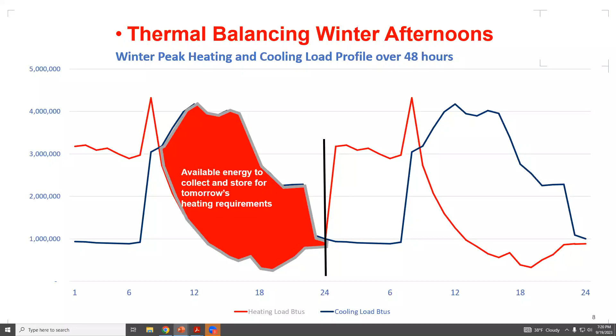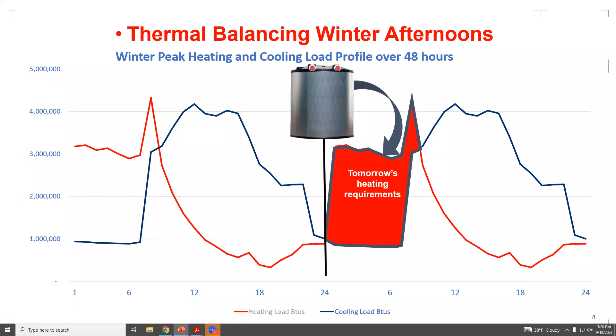Just to clarify, you're modeling a typical office building with an interior zone and an external zone. Yeah, correct, that's a good clarification. A typical Class A office will have perimeter heating loads in the winter and interior cooling loads year round, so we'd traditionally see a load profile like this. What this means is you have the ability to flip-flop where your heat source and your heat sink are within a building.